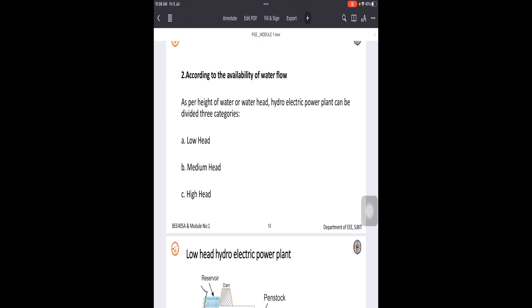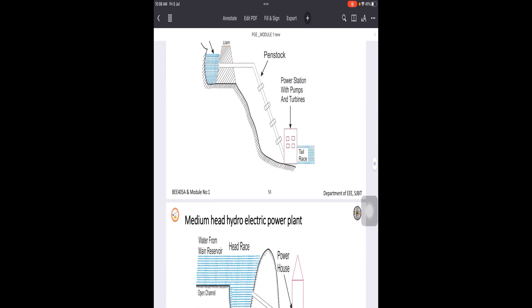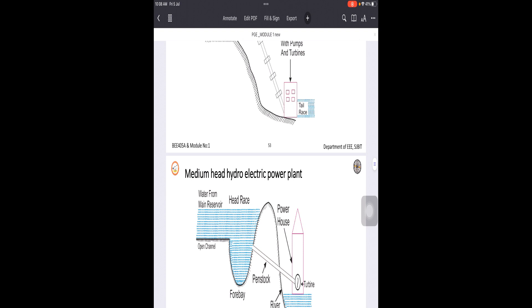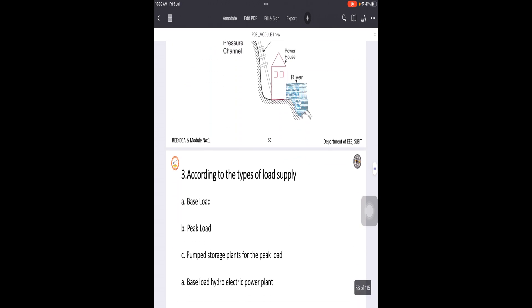Depending upon what type of power plant is suitable, these designs have been established. If the head is less than 10 meters up to 50 meters, we call it a low head power plant. From more than 50 meters up to 200 meters, it is called a medium head power plant. More than 200 meters difference is called a high head power plant.